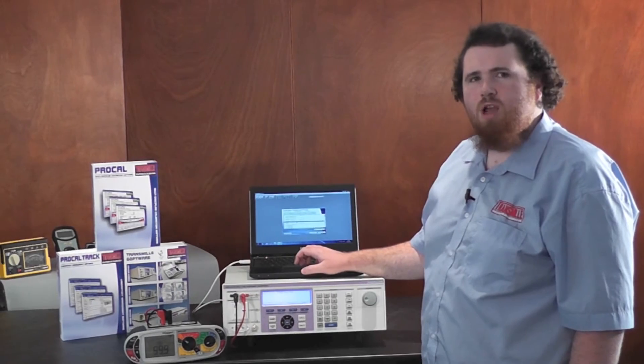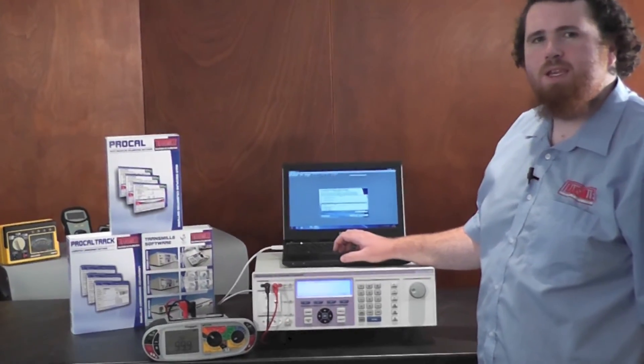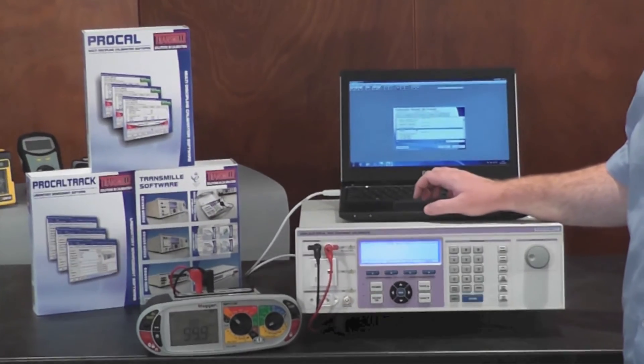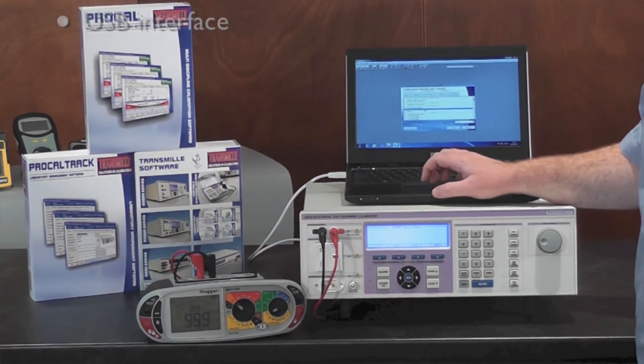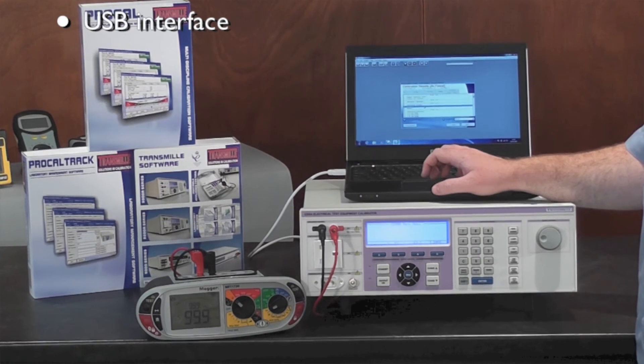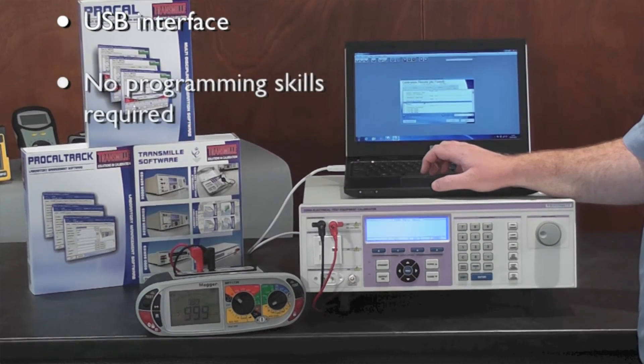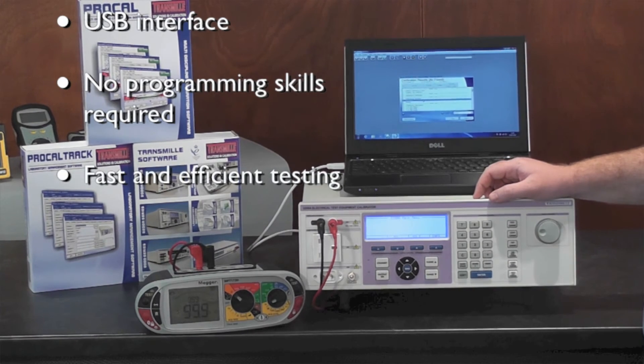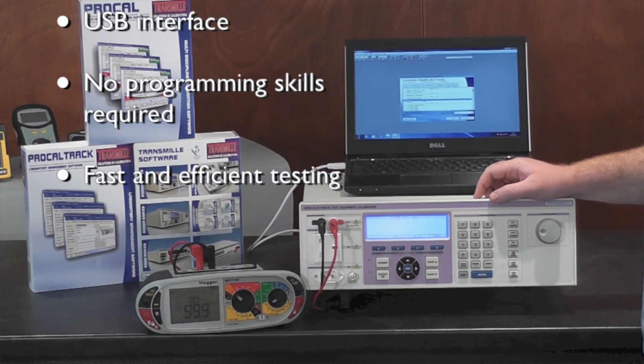The Transmille 3200A comes fitted with a USB interface as standard, enabling fast and easy connection to a computer. When connected to a computer running our ProCal software, procedures can be written that automatically control the 3200A, enabling fast calibration of testers.